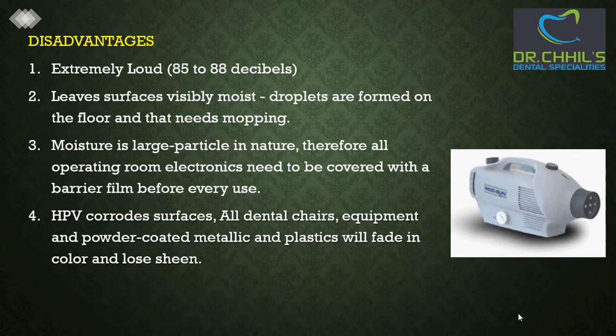Coming to the disadvantages, it is extremely loud and leaves surfaces visibly moist. Droplets are formed on the floor that need mopping. Moisture is large particle in nature, therefore all operating room electronics need to be covered with a barrier film before every use. The HPV corrodes surfaces; all dental chairs, equipment, and powder coated metallic and plastics will fade in color and lose their sheen.